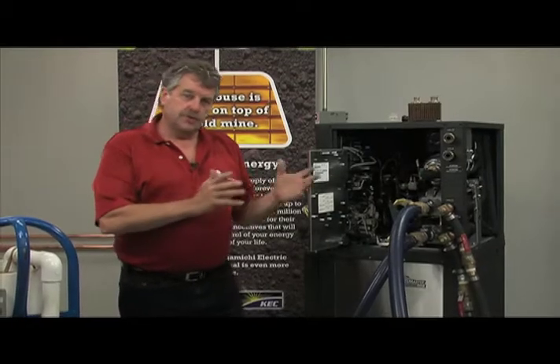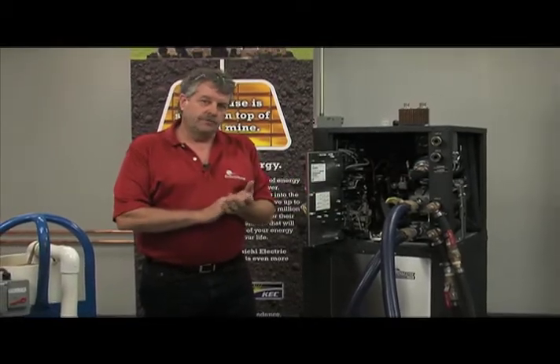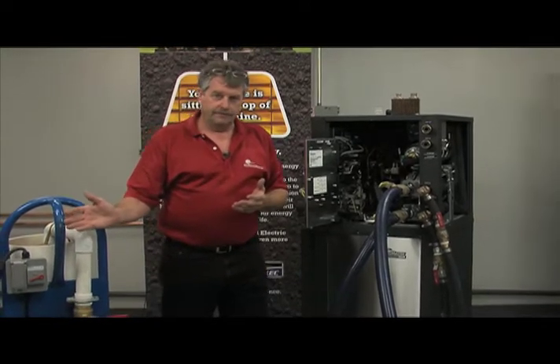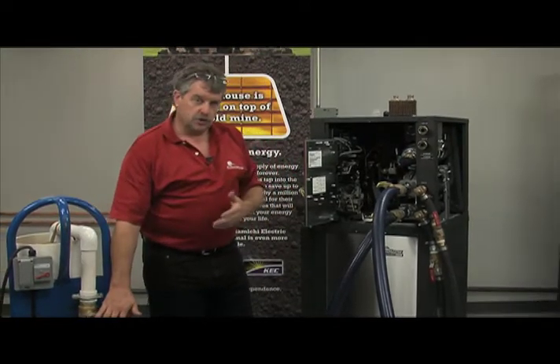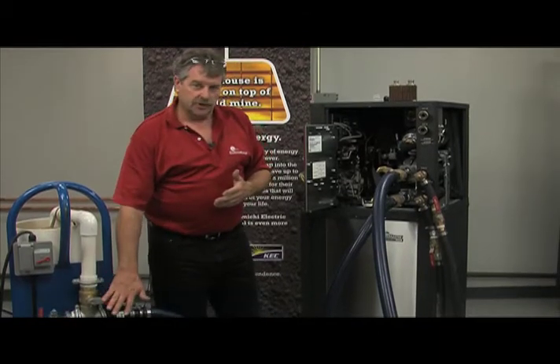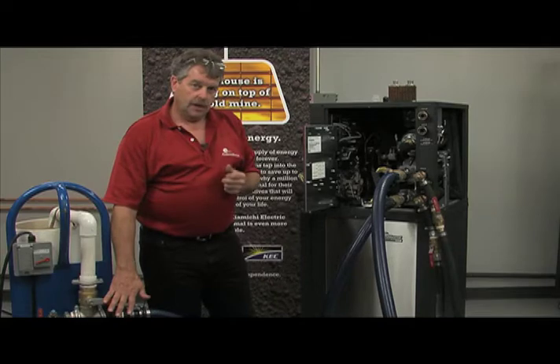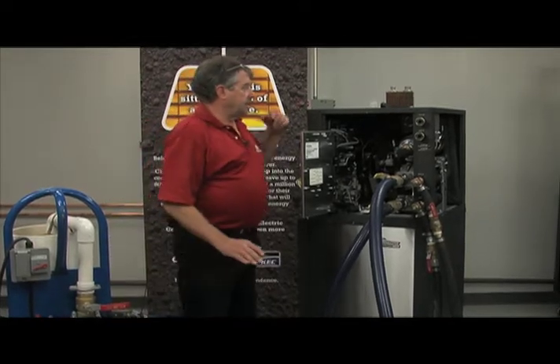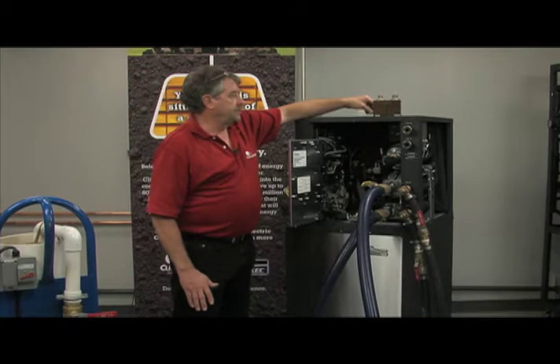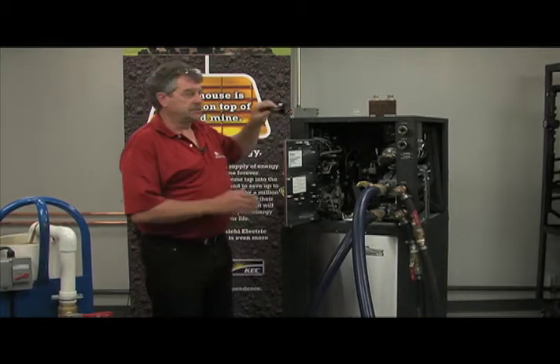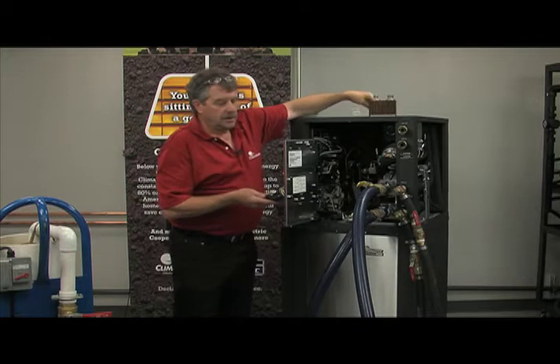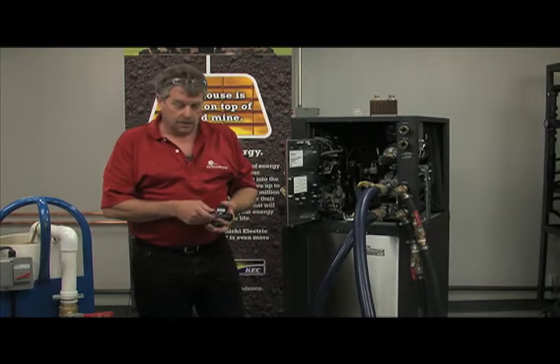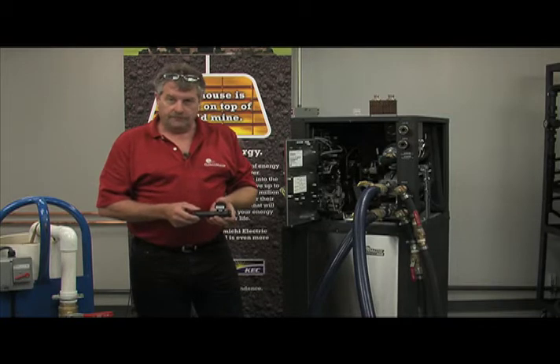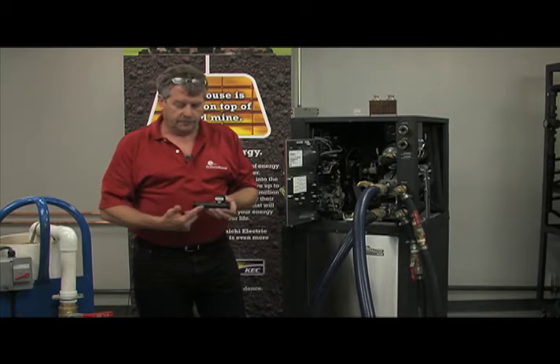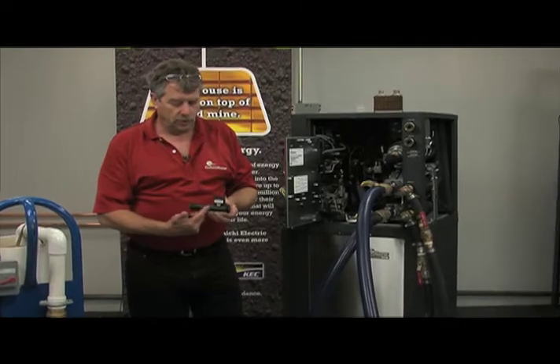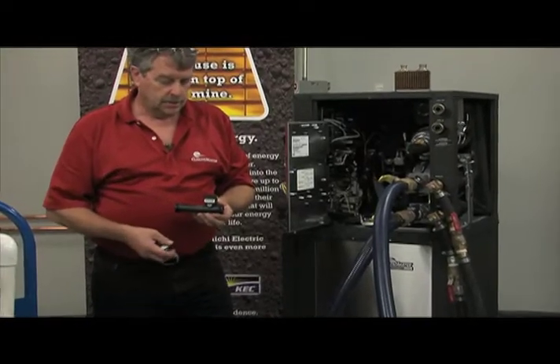So now we're ready to flush the inside of the unit, and a few of the procedures we want to make sure you follow. I have our flush cart turned off, and it's really important to notice that I have the return valve going back into the flush cart, that is also isolated. It's shut off from the unit. And the reason this is important is that there are some components inside this heat pump that have some sensitivity to flushing procedures. In particular, in our vFlow with iGate Connect and EXM board, we have a Grundfos flow and temperature sensor. So here's the actual flow body, and then here is the sensor.